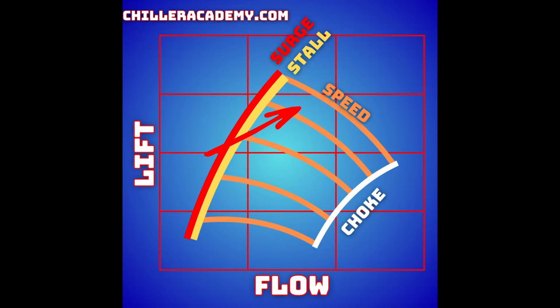So if our compressor is running at its minimum speed, so you've got low flow, low lift, so you have a low load with low lift, that also could mean on a variable speed compressor we have a really low RPM. That's where it's possible, especially if the liquid levels in the evaporator aren't quite balanced perfectly, or in the condenser, maybe our charge isn't quite perfect on the machine, that could send us right into a low end surge.